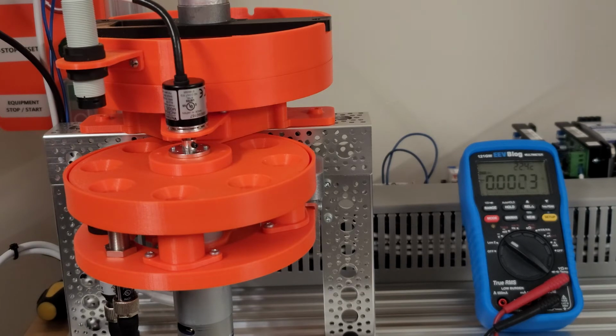As we saw on the calculator, that's about 16,800 and whatever. And I have exactly that same number coming out of the scale. So as far as the SCP instruction is concerned, and as far as what's going out to the program, the actual output is half of 10 volts. So it should be about 5 volts.